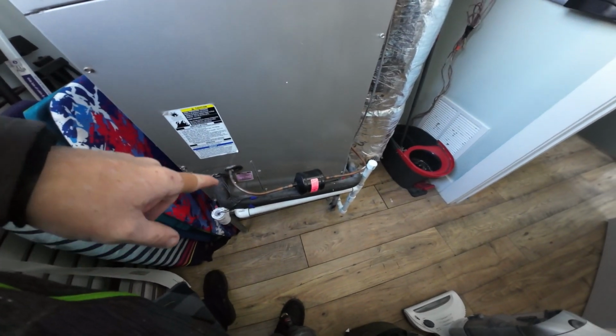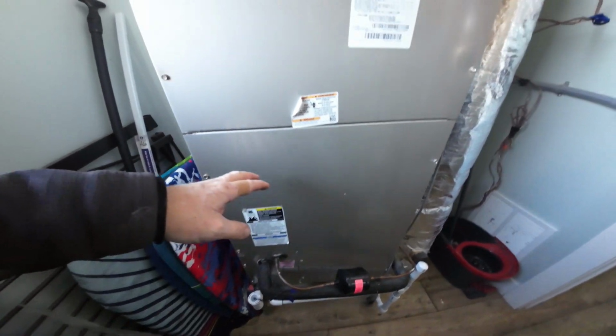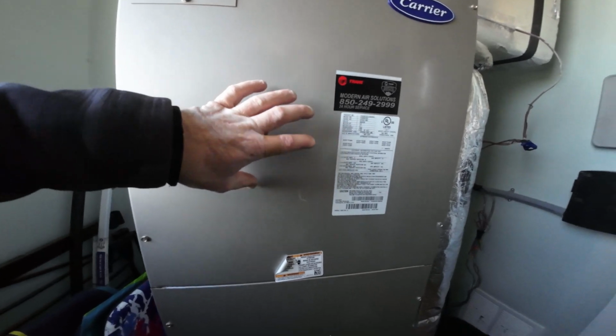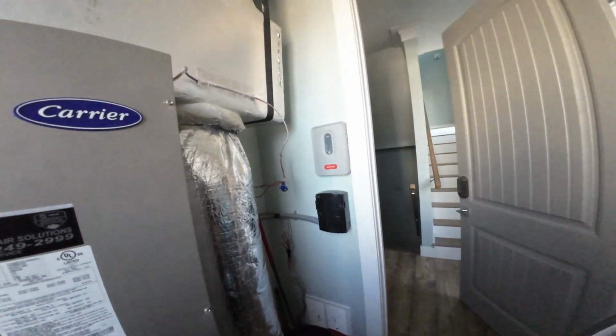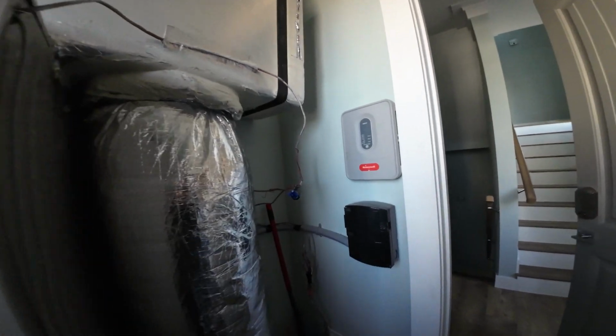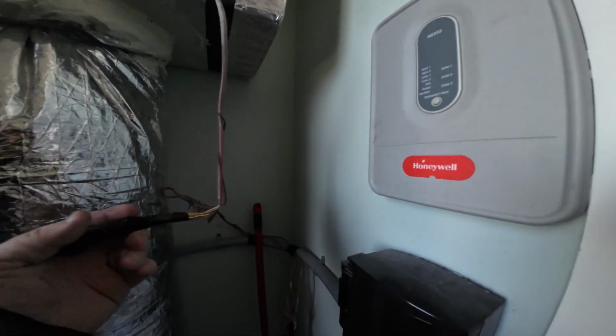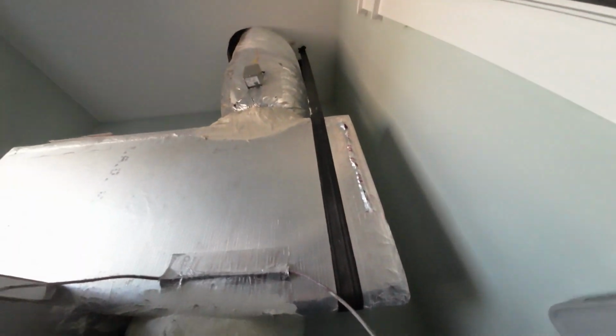This thing is missing the filter. I'm going to recommend a pull and clean on that coil — it's pretty caked up — and a pull and clean on the blower. Then if they want this back running like it should, we can replace the dampers.